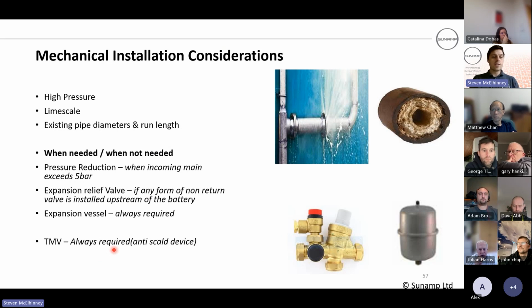So some installation considerations. We've talked about existing pipe diameter runs and making this plumbing system more efficient. Hard water areas: if you're exceeding about 150 parts per million, we do recommend having some form of descaler or water conditioner in there as well. High pressure: you're converting from a low pressure system, if it's tank fed, to high pressure. So you've just got to be aware of any lead pipe or poor fixtures that might be in the property. If you convert it, the customer might get a leaking tap, or the ball cock in the toilet might start passing as well. So again, you just need to make the customer aware.